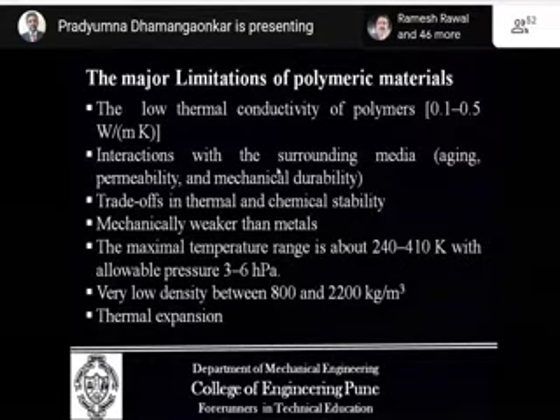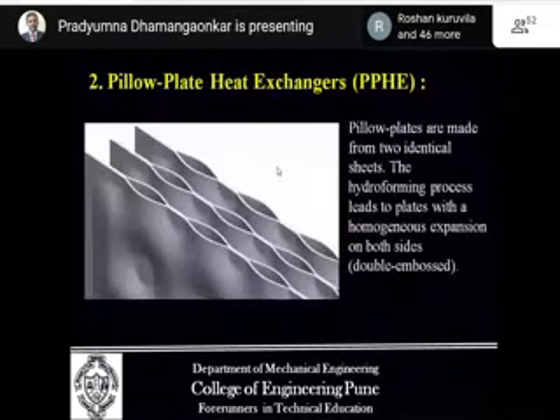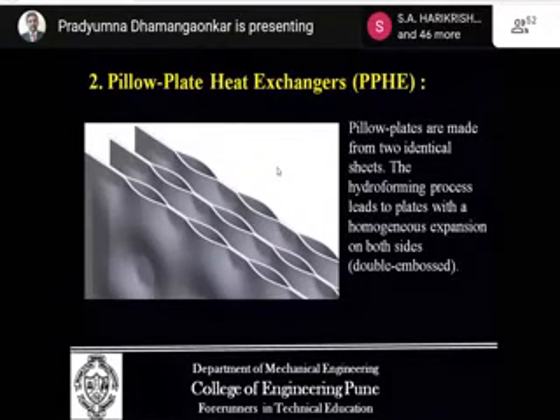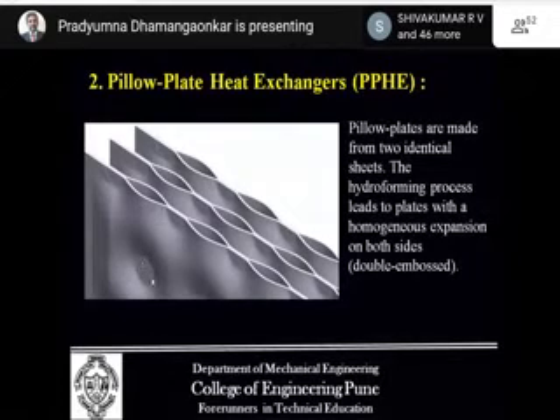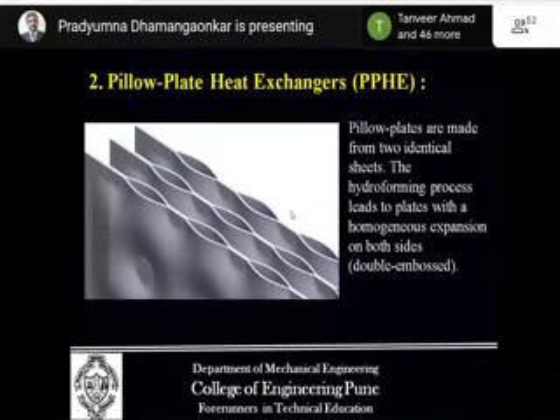lead to a deformation. The second is the pillow plate heat exchanger. It is a really innovative heat exchanger in which, as shown in the figure, the two plates are fixed at some intermediate spots so that a hollow space is created. Through this hollow space the fluid will move and get in contact at the contact surfaces. And these heat exchangers nowadays are used even in power industries, polymer industries, refineries.